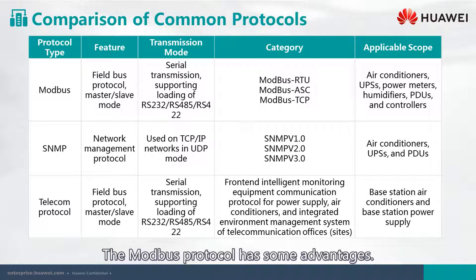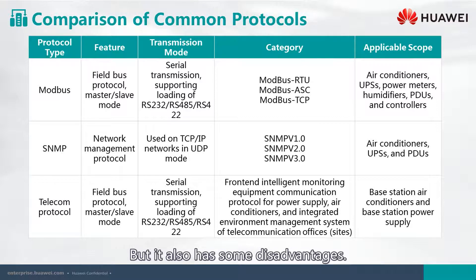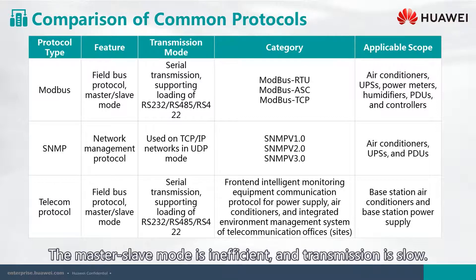The Modbus protocol has some advantages. For example, it is standard and open, it can support multiple electrical interfaces, and the frame format is simple and easy to use. But it also has some disadvantages: the Master-Slave mode is inefficient, and transmission is slow.